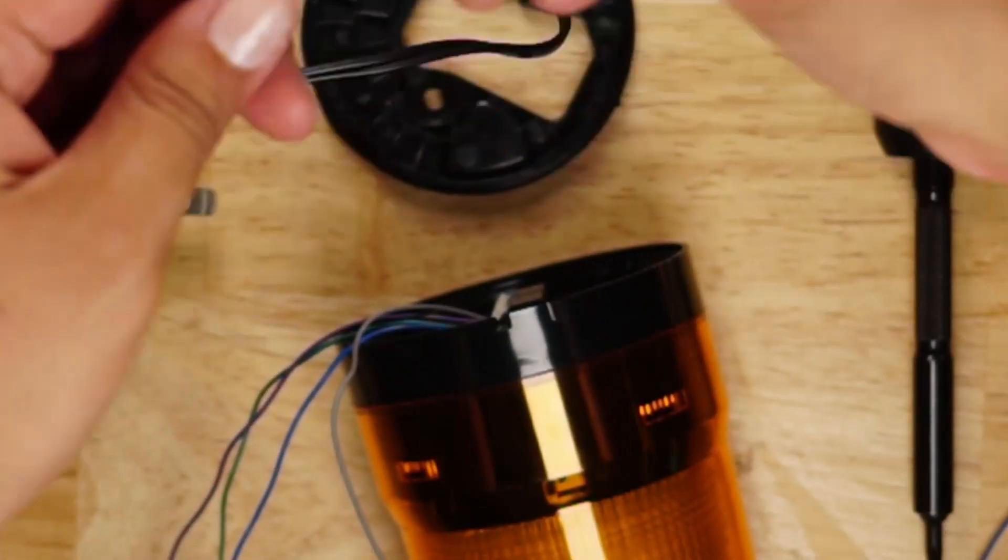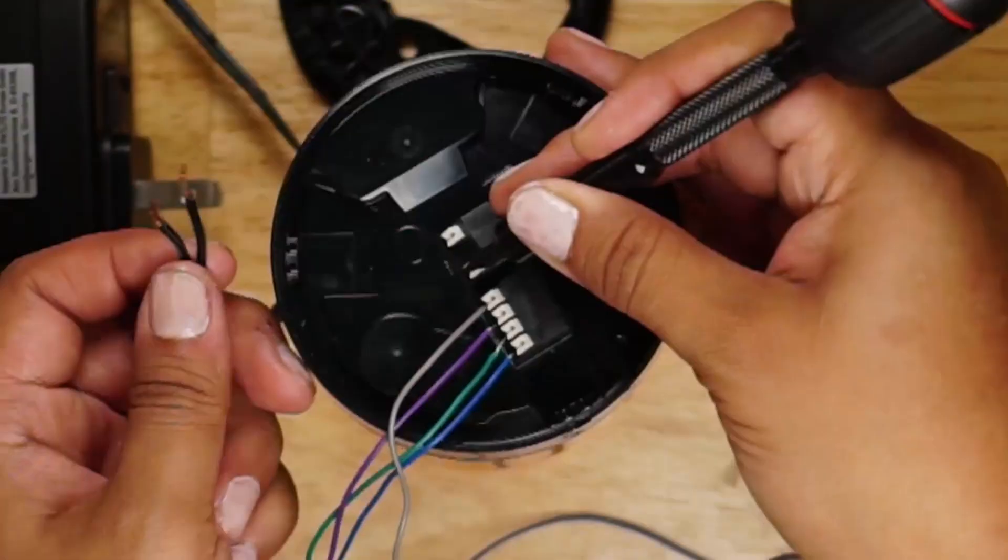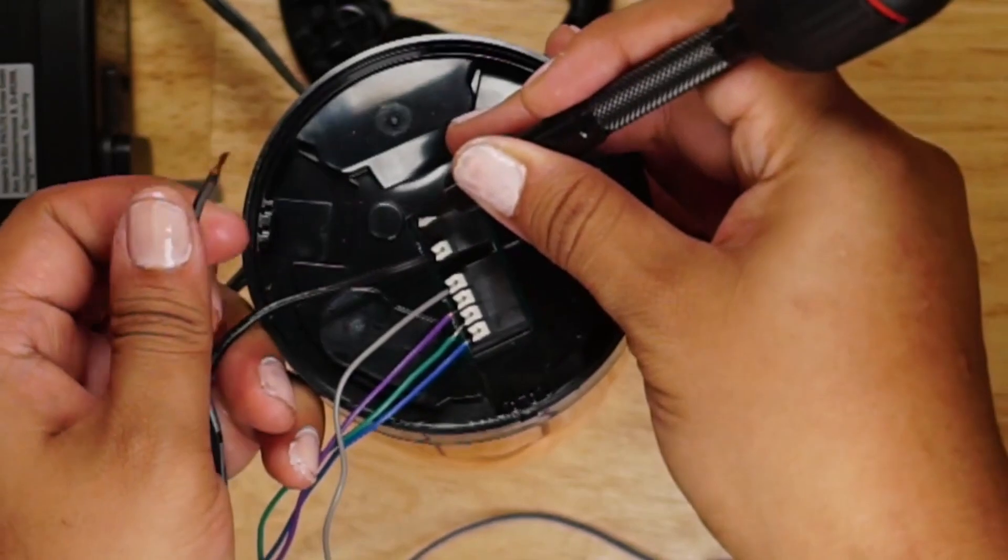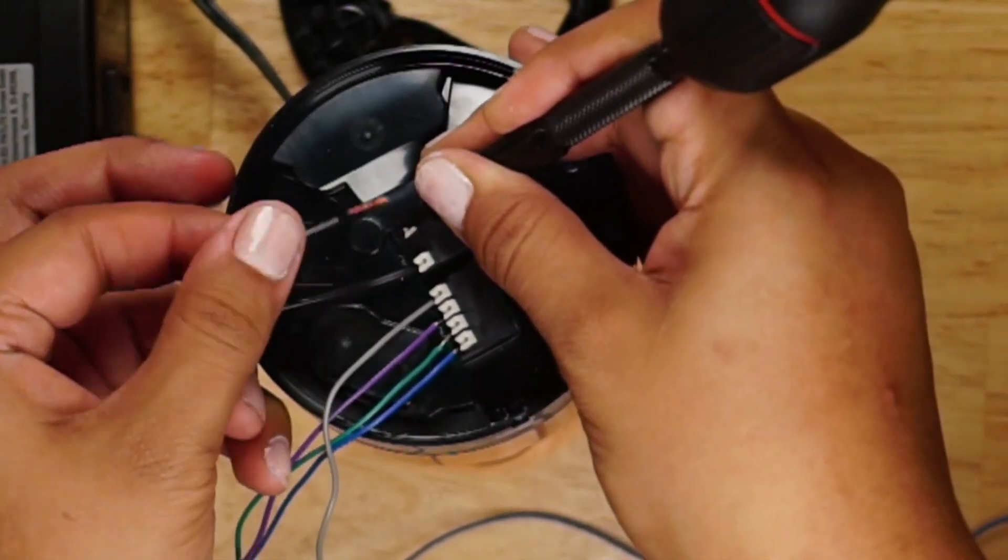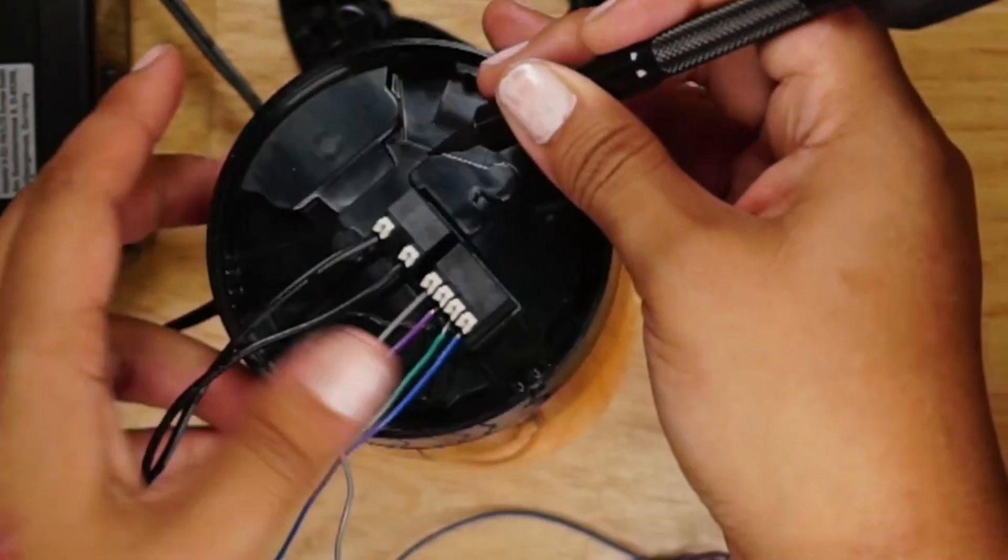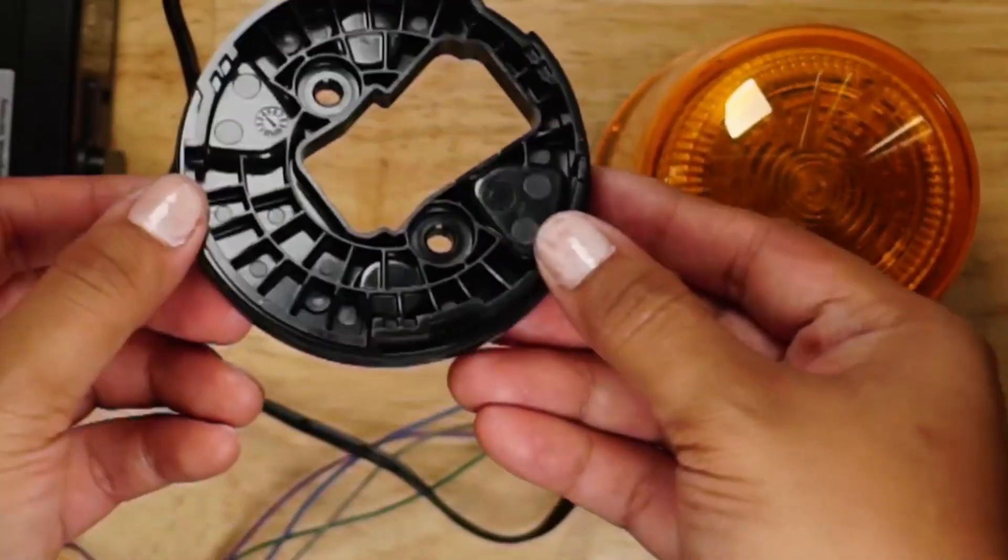I have my 24 volt DC power supply unplugged. I am taking the two wires to the power terminals. The beacon has no polarity, meaning 24 volt DC can go to either terminal and negative to the other. For final installation use the mounting bracket.